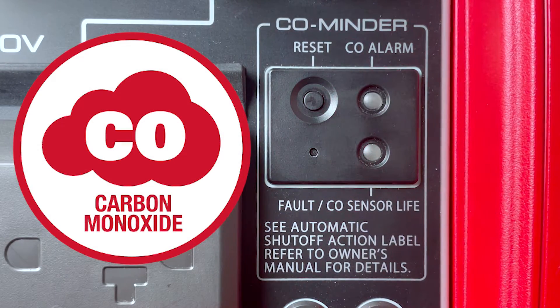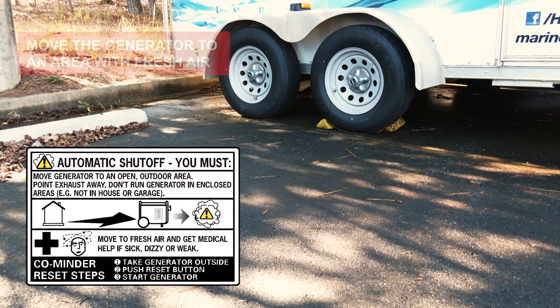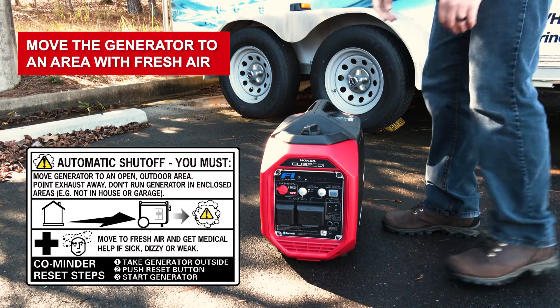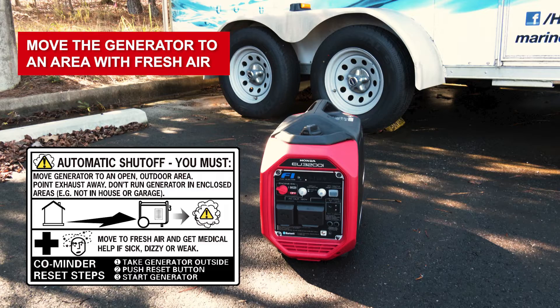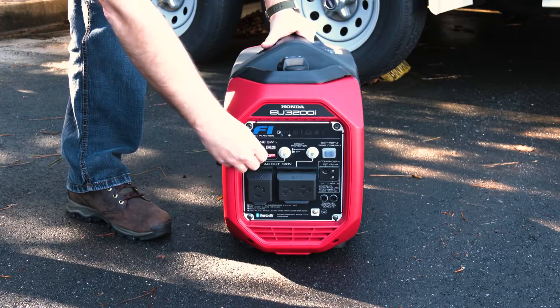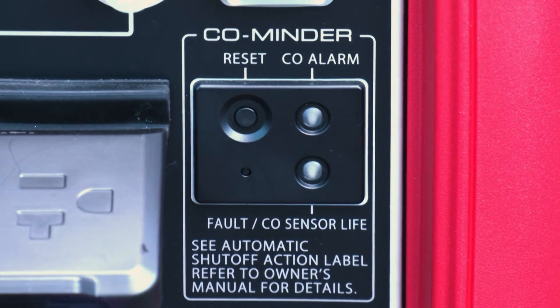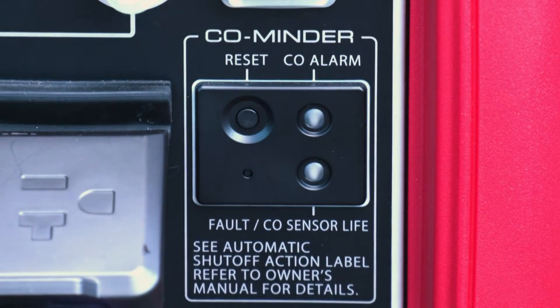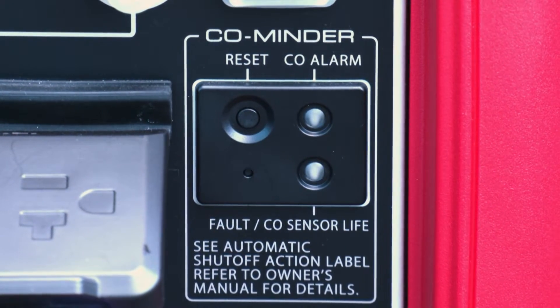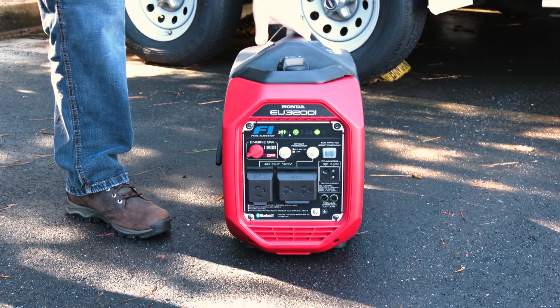The EU3200i is equipped with a CO minder system that is designed to shut off the generator when high levels of carbon monoxide are detected around the generator. When the engine is automatically stopped by the CO minder, move the generator to an area with fresh air and away from any device that may be emitting carbon monoxide, such as another generator. Press the CO minder reset button and then follow the standard procedures for starting the engine. When the CO alarm indicator or the fault CO sensor life indicator flashes, press the CO minder reset button to turn off the indicator. Note that after the engine is stopped by the CO minder, the generator cannot be restarted for approximately 30 seconds.